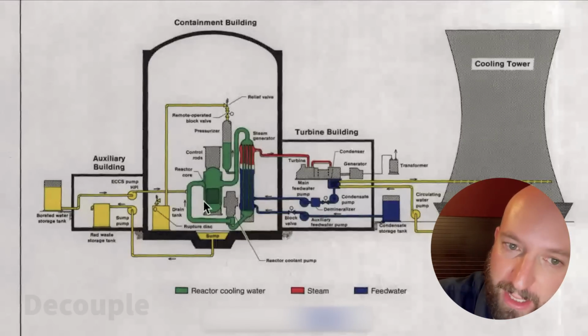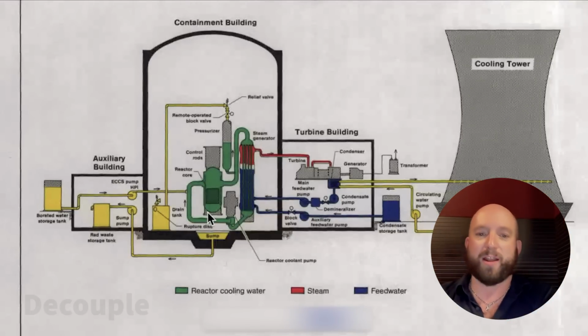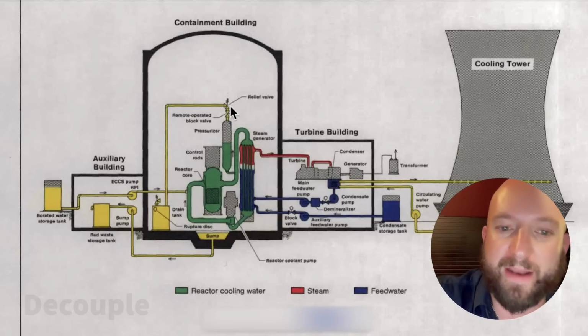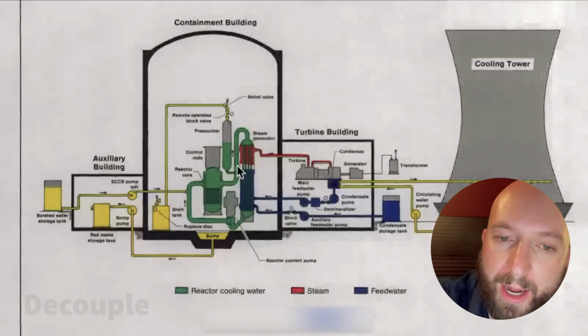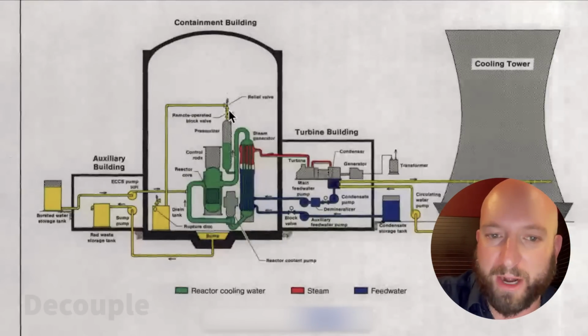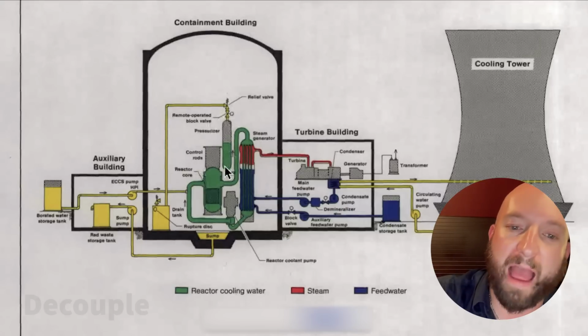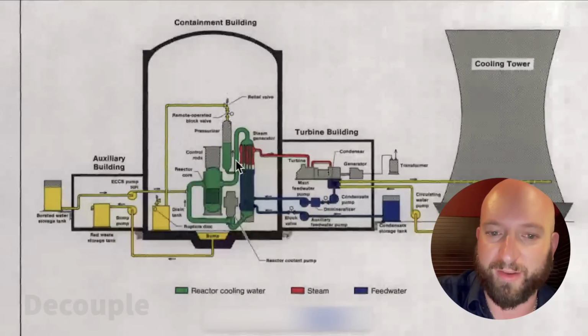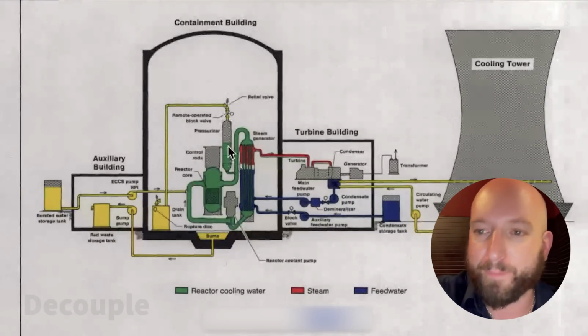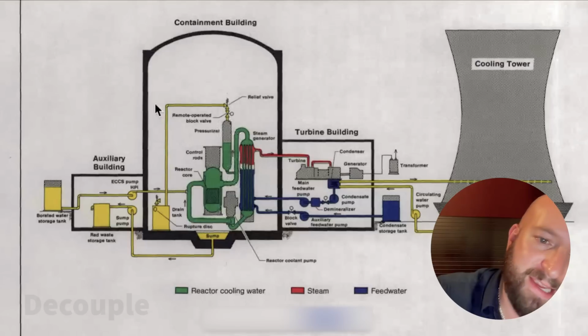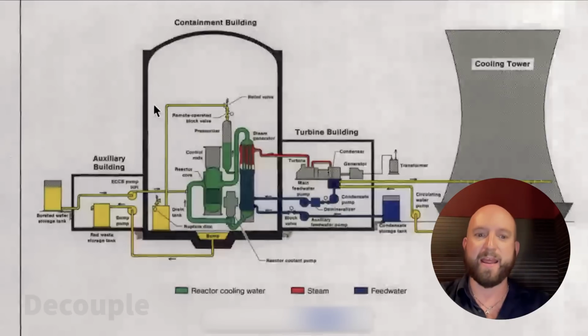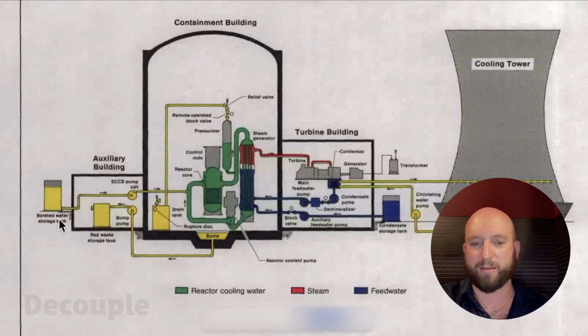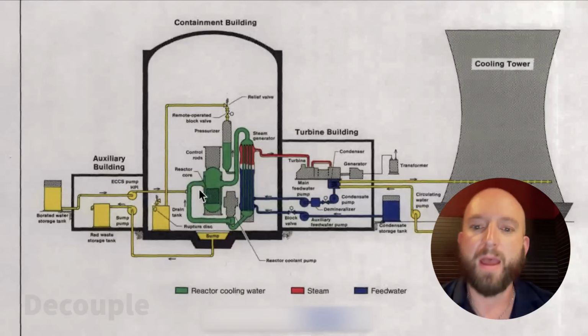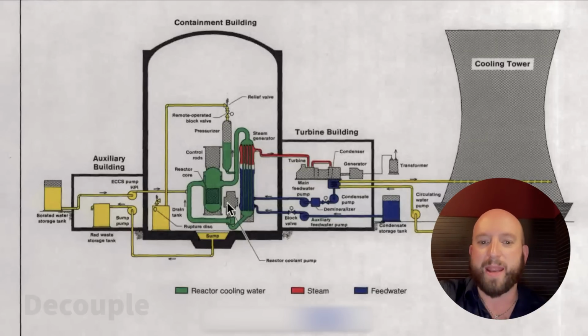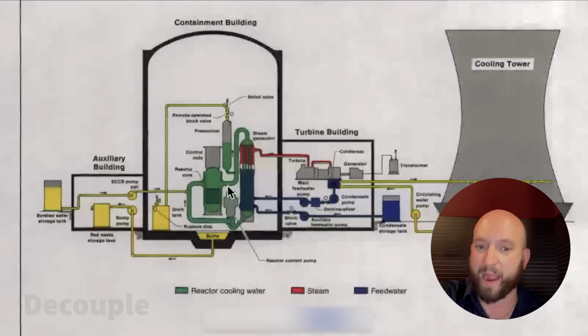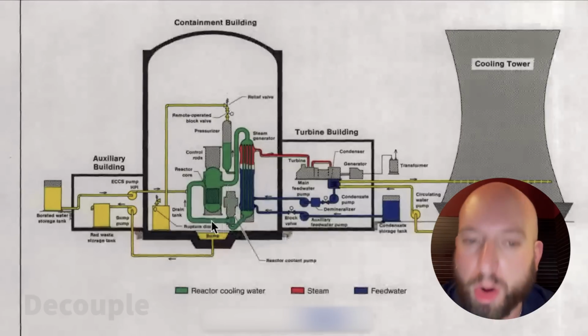that actually breaches the RPV. And furthermore, ironically, the operators at various times, even as they're recovering from the accident, recognizing what's going on in this situation, open that pressure relief valve a couple of times in order to have an alternative way of cooling the reactor coolant system. Basically by feeding and bleeding, it's called, essentially letting off steam out of the reactor coolant system. They can take away heat and compensate for that lost cooling water through the high pressure injection system, because they can't run the reactor coolant pumps until the system is refilled. They can't run these pumps because there's way too much steam and water in the system.